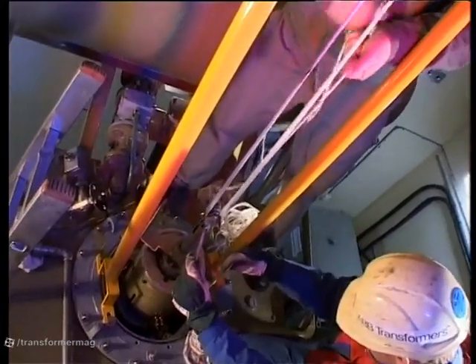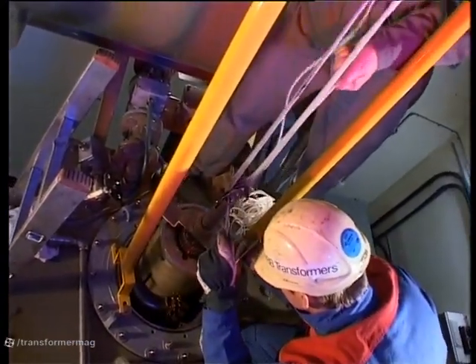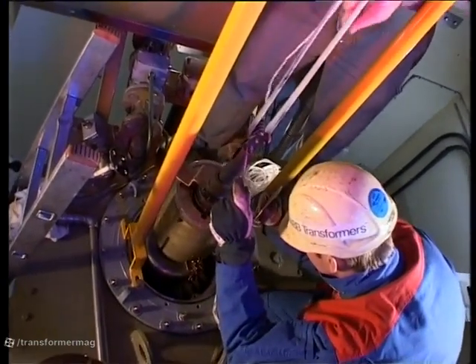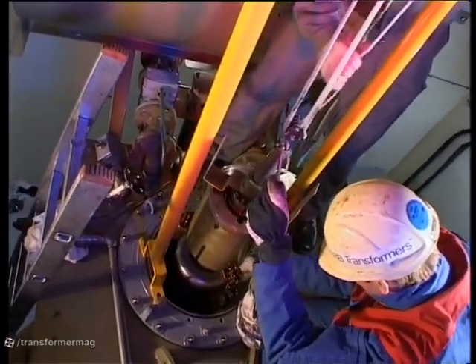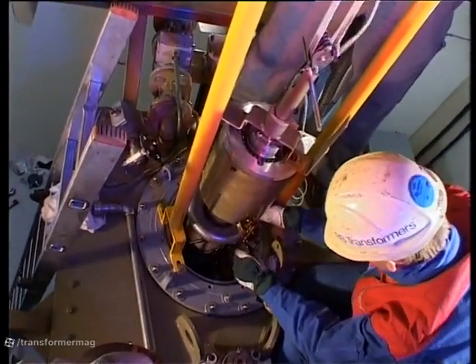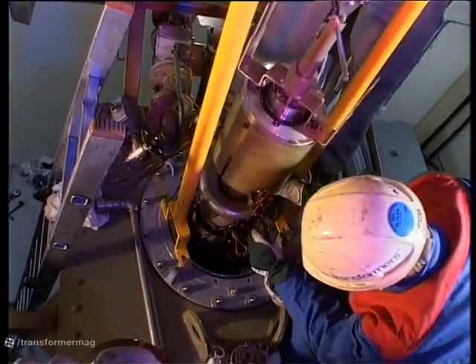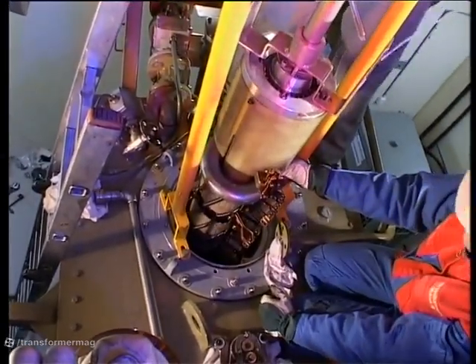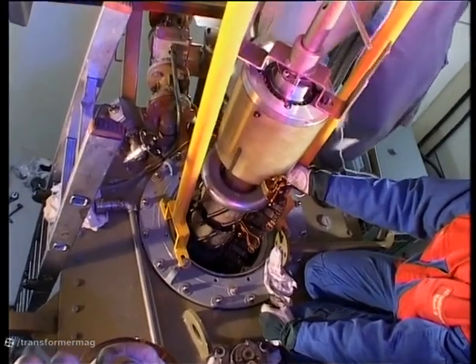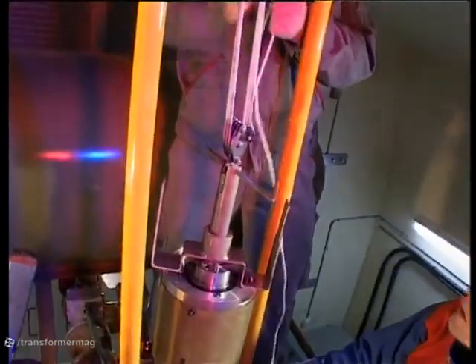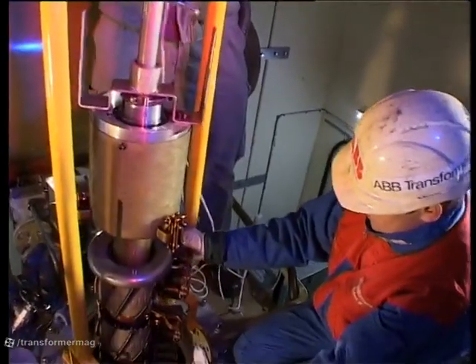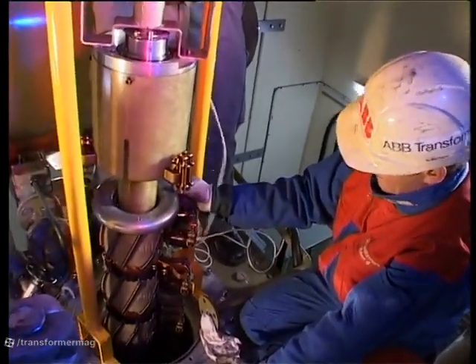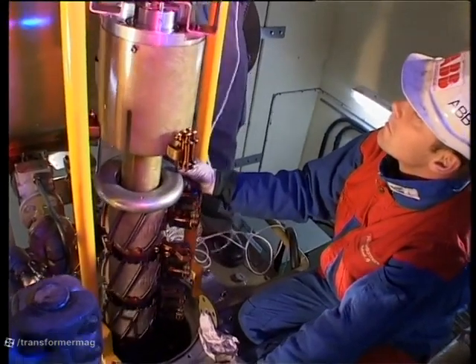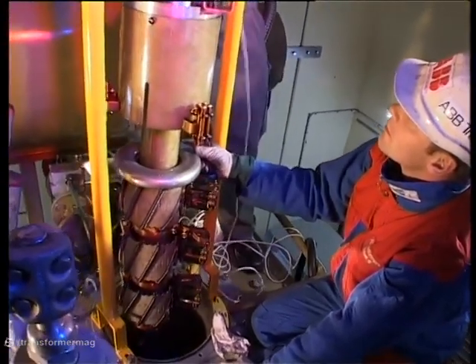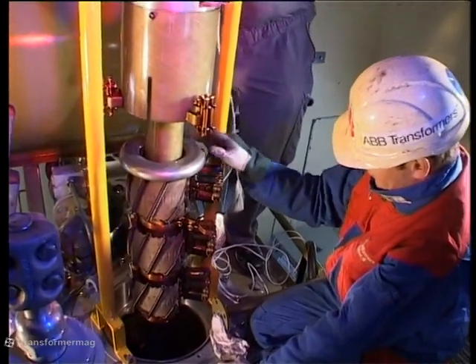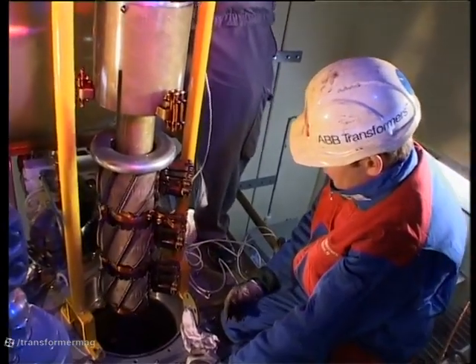When lifting the moving part of the tap changer, keep it still, otherwise it may stick. If it sticks, don't try to force it. Back off a bit, look down, and adjust so that all parts are free. Lift carefully until all parts are out of the cylinder. If you want to lower the selector switch to the floor, rest it on something soft.